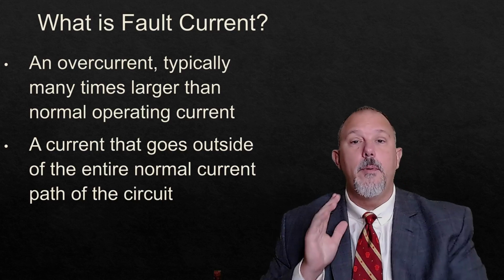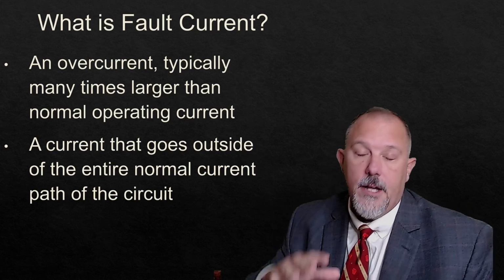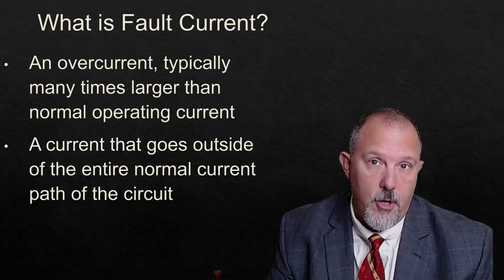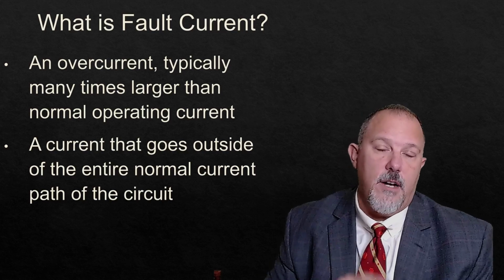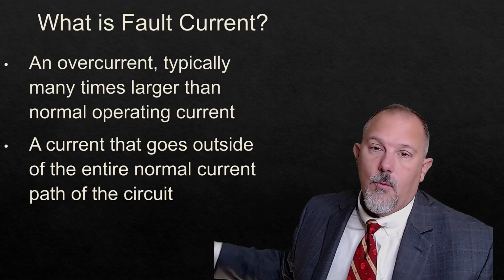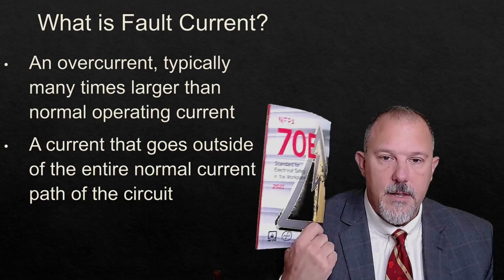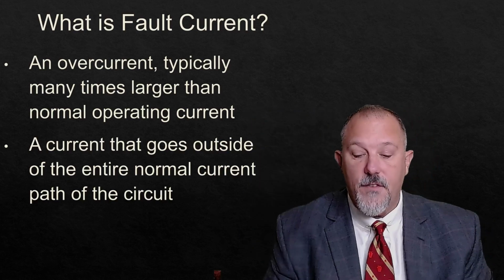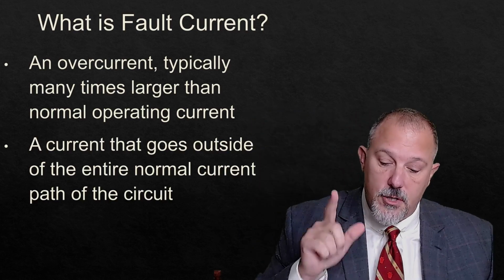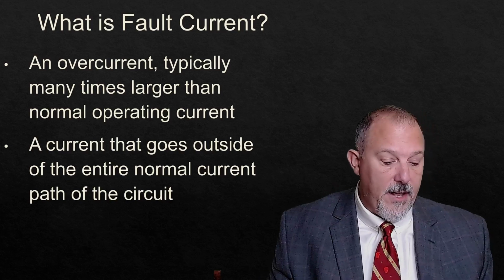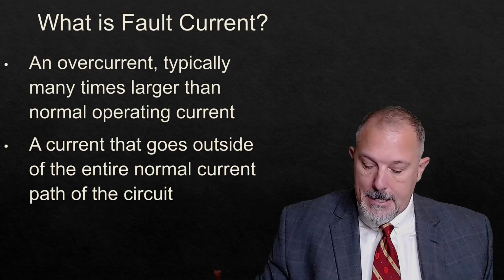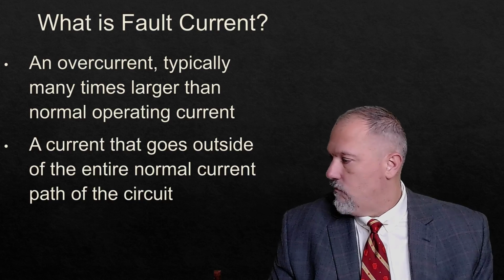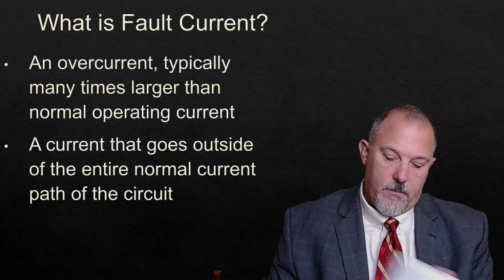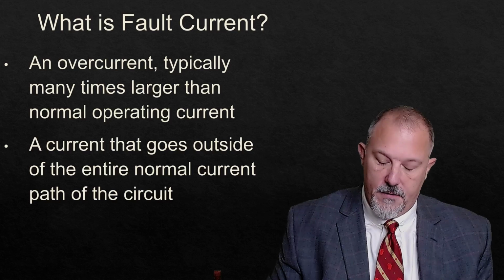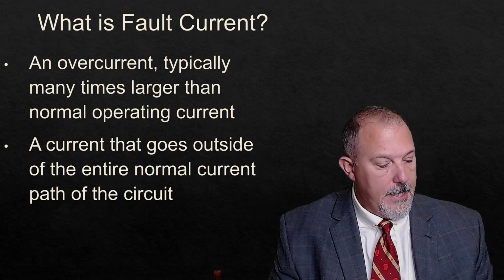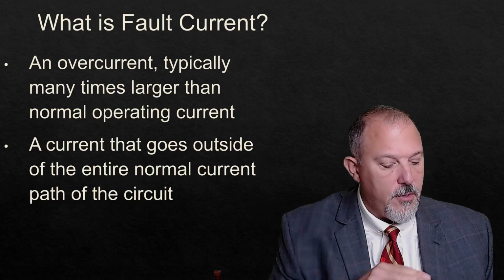Now, let me give you a little bit of background. Those two terms are new for the 2020 version of the National Electrical Code. And where do we get those from? The 70E document is the first place that introduced the terms fault current and available fault current. I have the 2021 version of that document, and I'm just going to look. And there is fault current and fault current available.